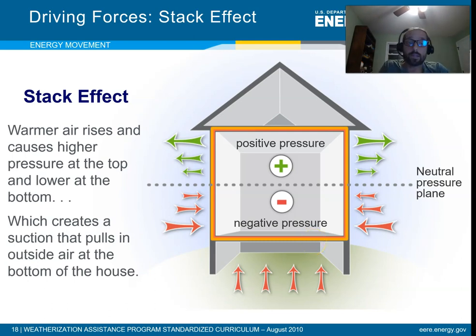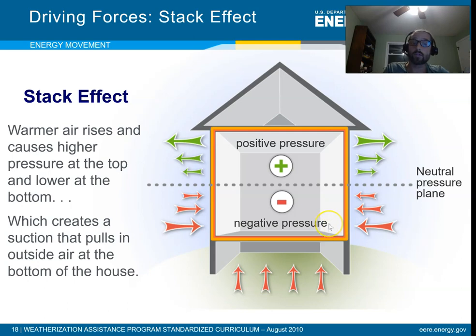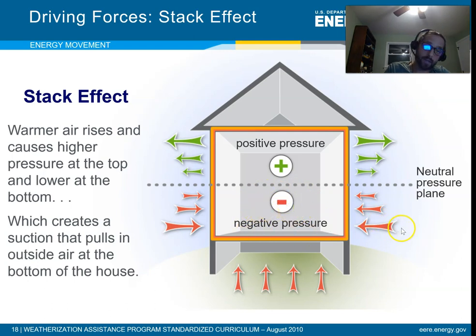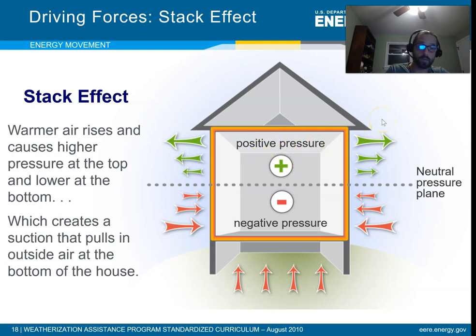Why do we care? At the top of the building, there's high pressure with respect to the outside; at the bottom, there's low pressure with respect to the outside. Air moves from higher to lower pressure areas, so the result is a negative pressure zone down low — negative with respect to outside — which pulls outside air into the bottom of the building. The opposite happens at the top, where air moves from inside to outside.